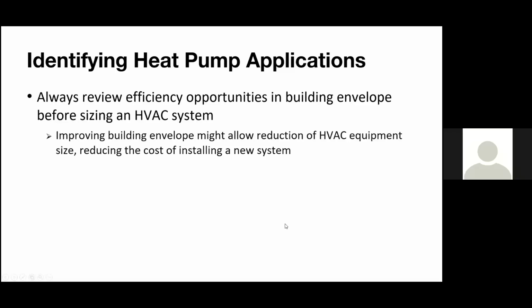but before you're even designing a heat pump system, you need to look at the building envelope, because a lot of the time you can just take the low-hanging fruit and fix the building envelope to save you a lot on something else. You might put an initial investment down of, all right, let's improve the insulation, let's improve these windows. That is going to correlate directly to your heating and cooling and what you're going to be doing. It's actually going to save you upfront costs, because if your building is more tight, that means you're not going to have as much solar gain. That means you're not going to have a lot of heat loss. So that means basically your overall tonnage of your heat pump system is going to be lowered at first cost. You're not going to need as much. So that's just something to consider.